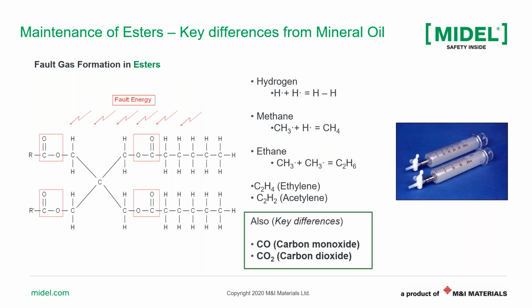For an ester, you have these ester groups, the oxygen, as you can see within the square boxes, and any fault will decompose this fluid to hydrogen, methane, ethane, ethylene, acetylene in a similar way as to mineral oil, but also you will add carbon monoxide and carbon dioxide. So these are the key differences between mineral oil and ester. You have these carbon oxides produced from faults involving only the liquid.